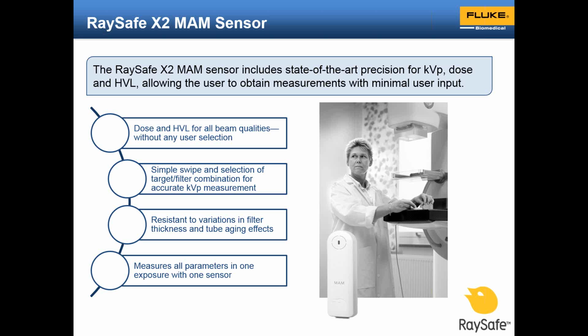One of the industry first features developed in the X2 is the ability to measure dose and half-value layer, or HVL, on any available target filter combination without any user selection. In other words, you don't have to tell the meter what you are measuring on to get accurate dose and HVL values. The only time you need to make a selection is when measuring kVp. And in this case, it's a simple swipe to the left, select the target filter combination from the menu, and take your exposure. We call it active compensation, which is just a clever way of saying the X2 MAM sensor isn't sensitive to variations in filter thickness or the effects of tube aging over time. You just get accurate readings every time, and as is the case with the RF sensor, you get all parameters in one exposure with just one sensor.